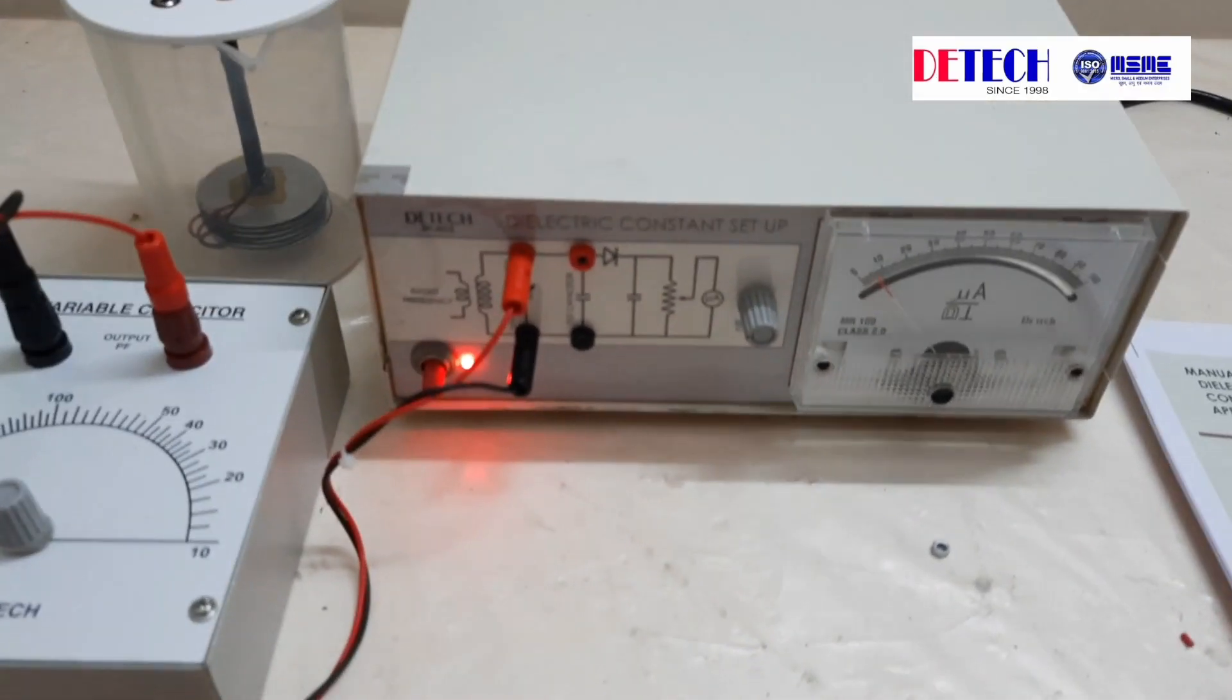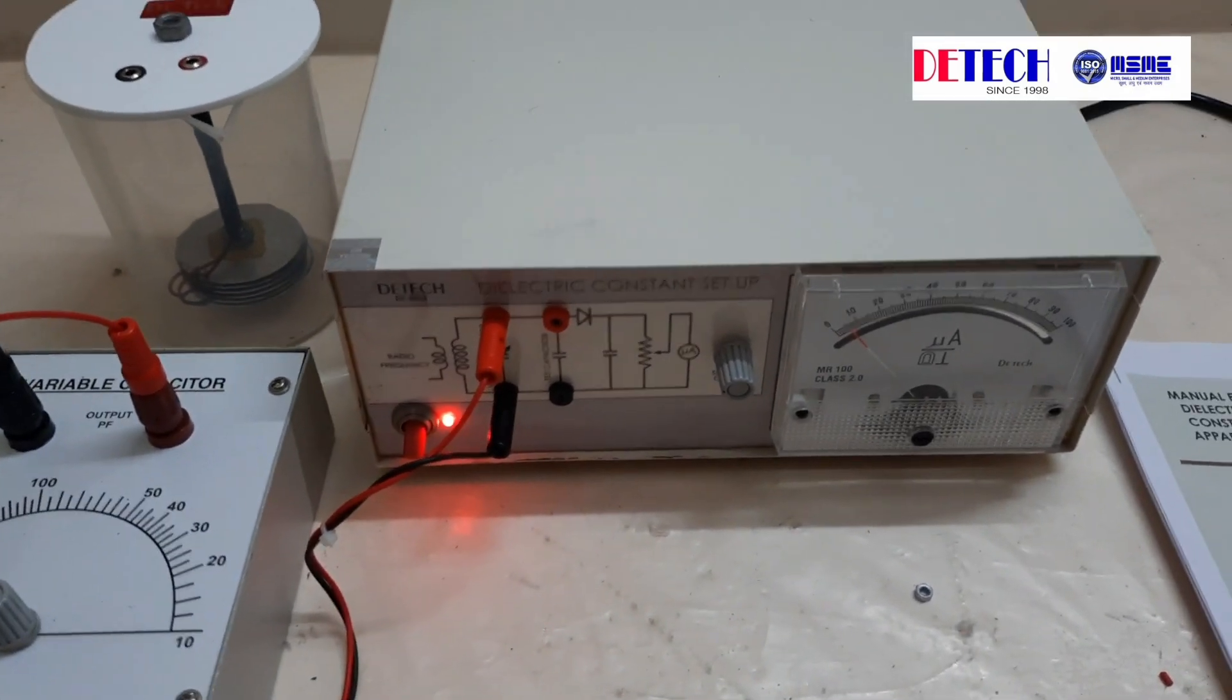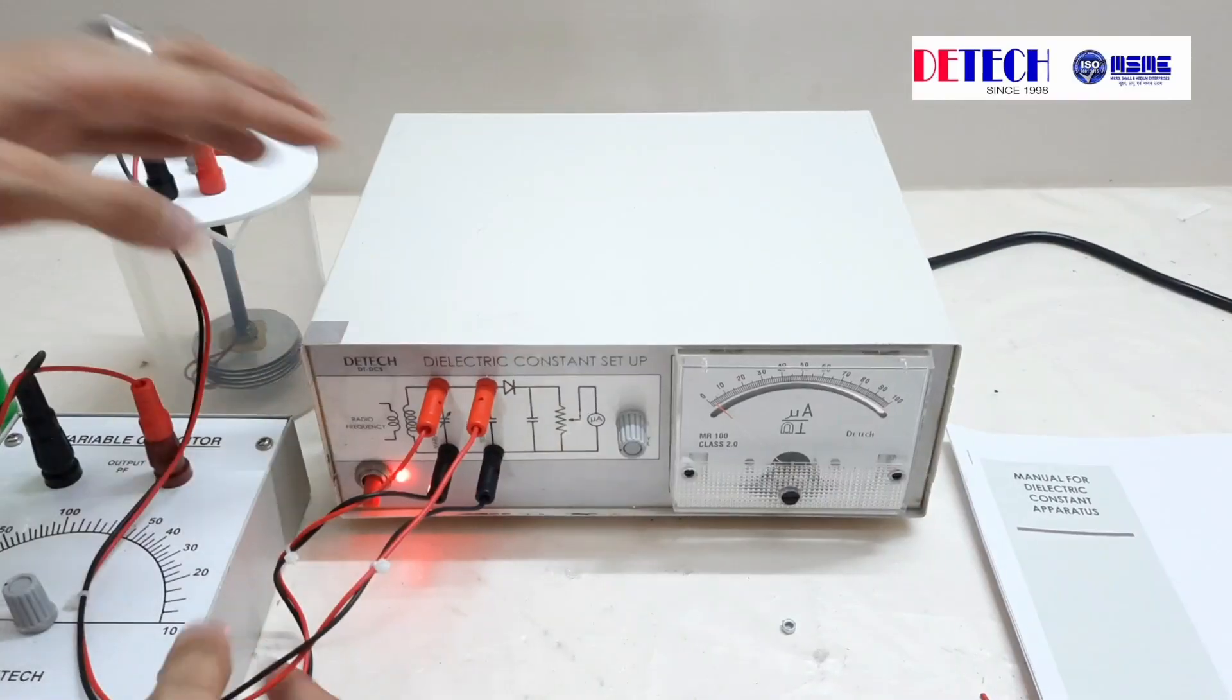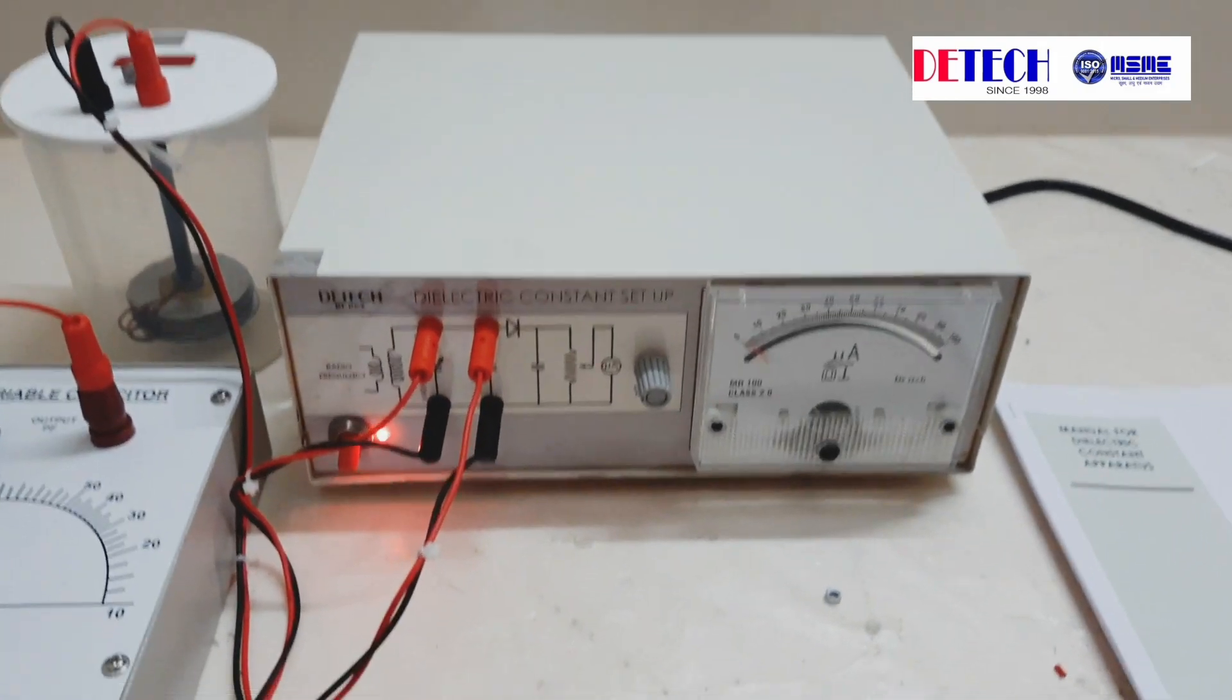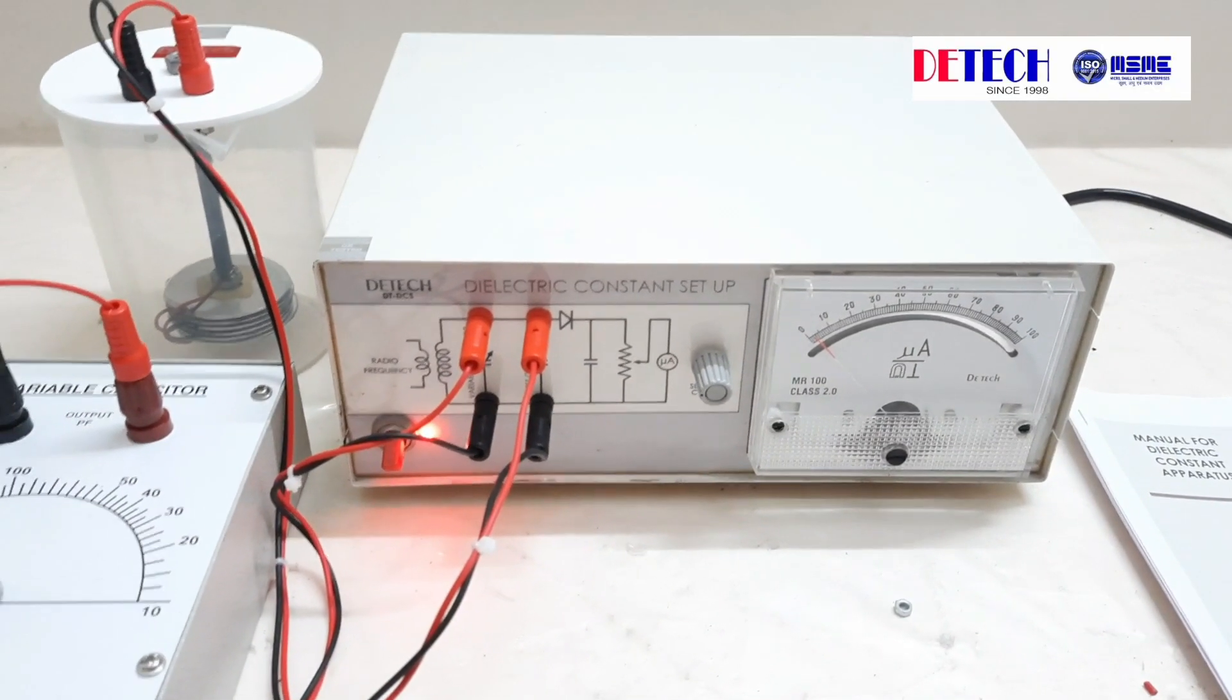We again change it and keep it at 270. Now let us connect the test capacitor. So the previous value that we obtained without the test capacitor was our value C1. Now C2 is the value with liquid dielectric in it.